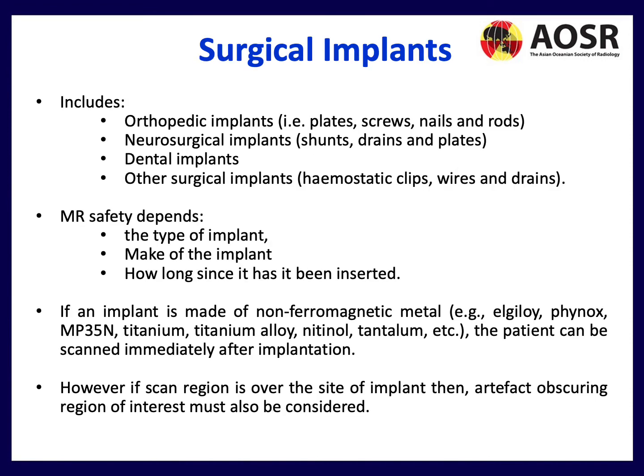Surgical implants we mentioned before. This includes orthopedic implants that can be plates, screws, or even rods. Neurosurgical implants, including the shunts, the programmable VP shunts. Dental implants. Now, MR safety depends on the type of implant, the make, but also, as I said before, how long since it has been inserted. So if an implant is made of non-ferromagnetic metal, the patient can be scanned almost immediately after implantation, but you have to check on a case-by-case basis. However, if the scan region is over the site of the implant, then artifact obscuring the region of interest must also be considered. Always think about your scan quality.